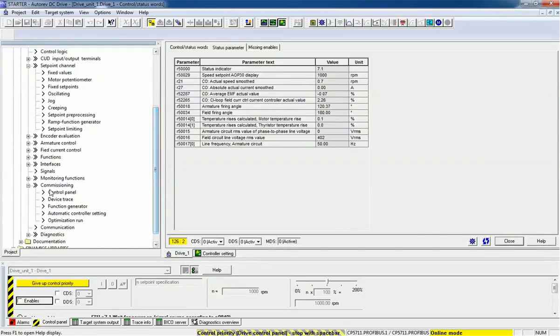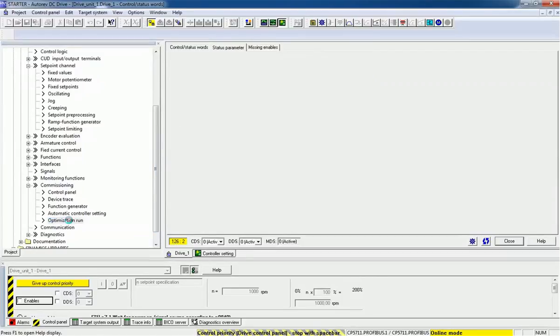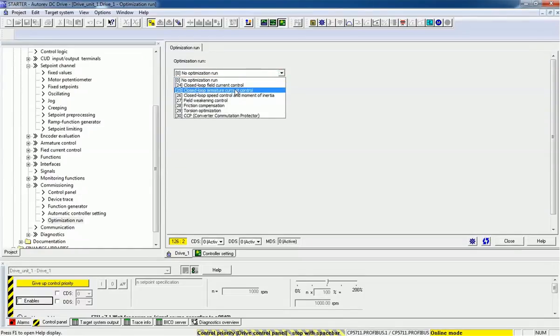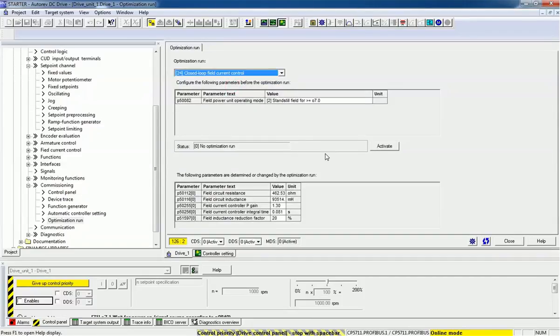From commissioning we have the option 'Optimization Run'. I will open this option and here we have different tests for optimization. First we will see closed loop field current control. Right now we have not connected any load with the DC motor so we are not able to do all optimization tests, but we will see some of them. For closed loop current control, we are getting parameters: field circuit resistance, inductance, controller gain, integral time, and inductance reduction factor.